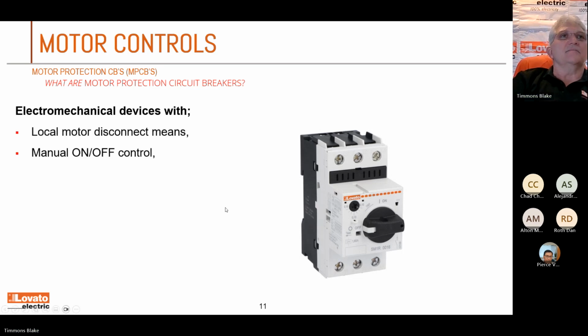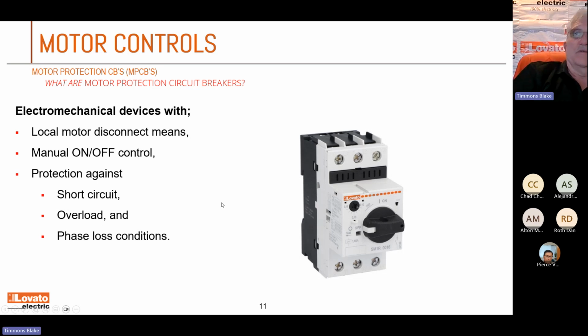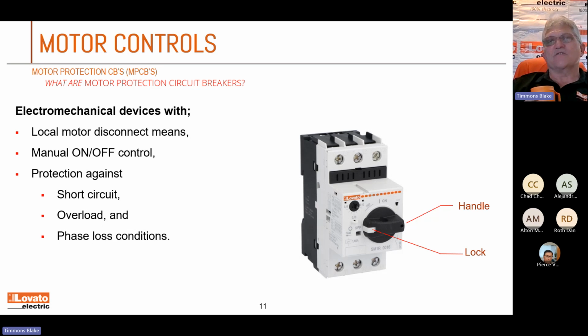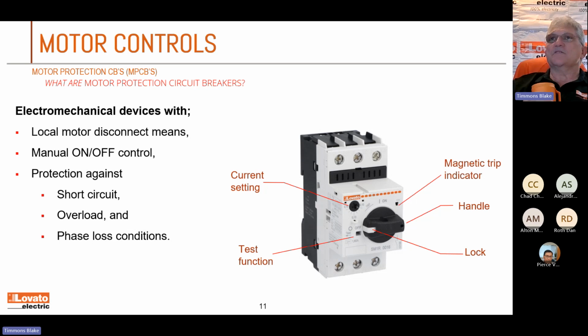It's got a disconnect, manual off and on, and it protects the motor. It's got a higher short circuit rating also, so a lot of times you can replace the motor fuses feeding the motor. Ours will also detect phase loss, so if you get a single phase situation, it'll trip out for you. There's a handle and it'll lock. Naturally, it's not going to be a real secure lock. It's kind of delicate. It's just enough to indicate to somebody else, hey, don't turn this on, I may be working on it. You have a test function on it, so you can trip that button to see if it's going to trip for you. You have the current setting I mentioned and a little magnetic trip indicator, so you just look at it and see if it's tripped.